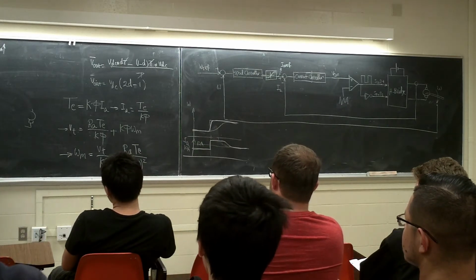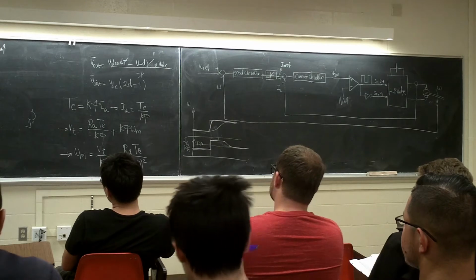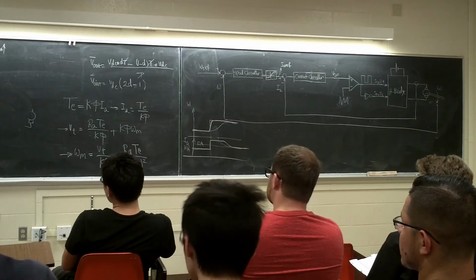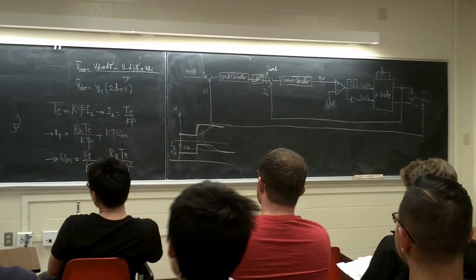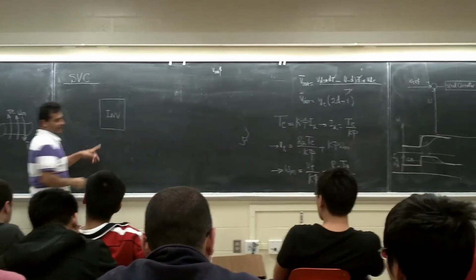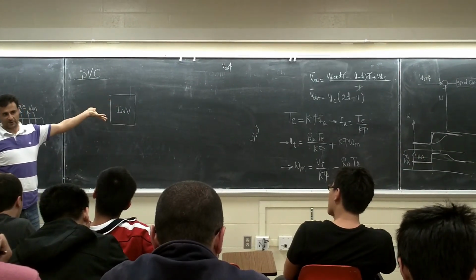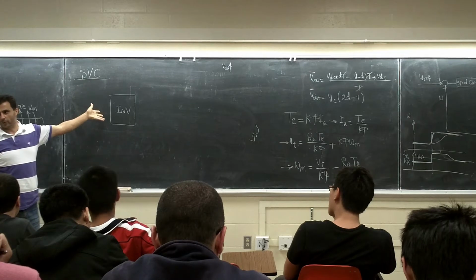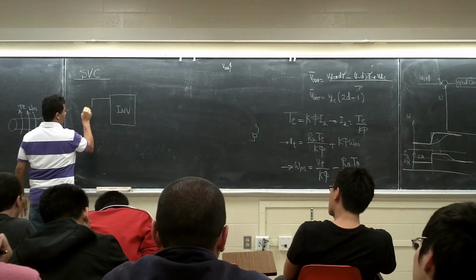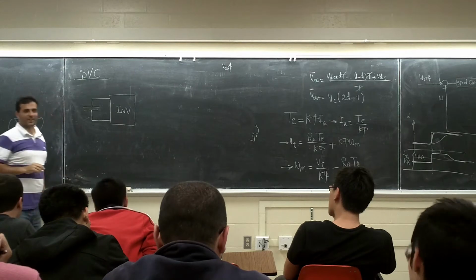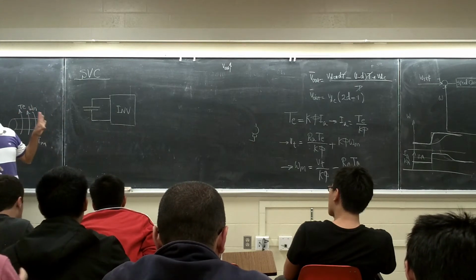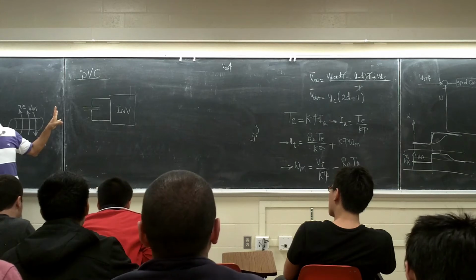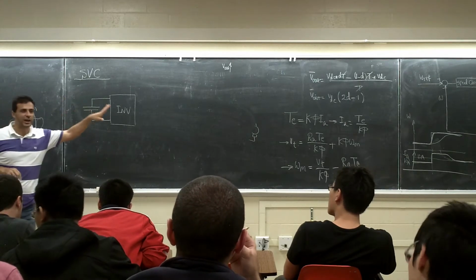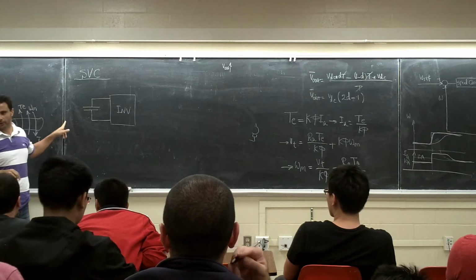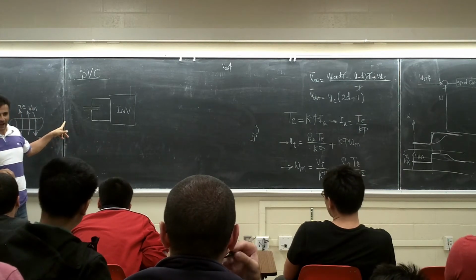SVC, they call it a static var compensator. SVC is this - I'm not going to put the detail here. This is the inverter, the three-phase inverter you guys know, but there is no value or anything, there is only a capacitor here. SVC is a static var compensator. This device is only going to inject reactive power because it doesn't have a battery or any energy source to inject active power.